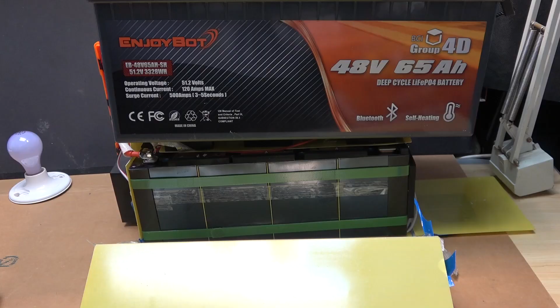Oh, it goes back up to 10. That means the sensors are warmed up enough, so it cuts off power going to the heating pad. Now we're charging again at 10 amp, and over here on the heating pad there's no power going to it, it's 0 on this side. The heating pad temperature is reducing—it was 45 degrees Celsius, now it's going down to 41, and quickly: 40, 39. Yep, so it's working great.